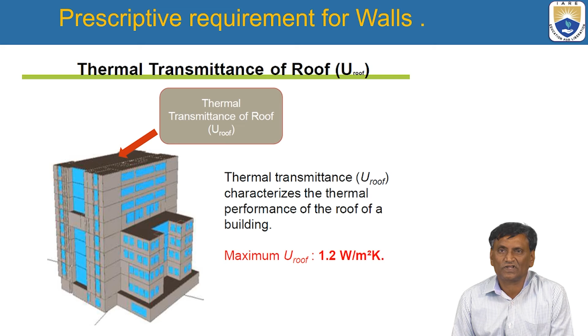Then what about walls? So, roof, what is the U value of roof? Different construction. If you only use RCC slab like 4 inches, that is 100 mm slab, your U value will be 3.6, which is not acceptable. You have to bring down to less than 1.2. Suppose you add to the concrete some kind of waterproofing and some RCC, some insulation, some slab, some tiles, then you can bring down the value to 0.62, which is less than 1.2, which is acceptable. Suppose you further insulate with expanded polystyrene, some kind of false ceiling, and some kind of aerated concrete, all that if you use, you can even bring down the value to 0.54. Lesser the U value, better is the building with respect to heat gain. So, less will be the AC load.